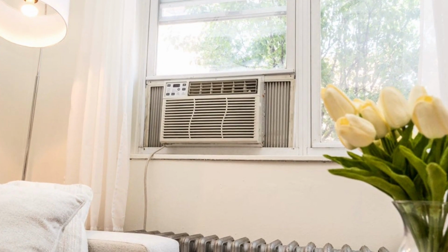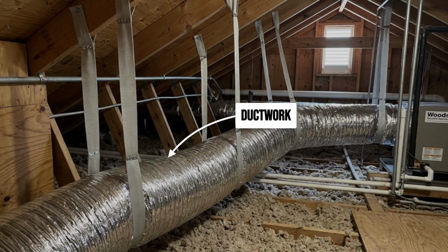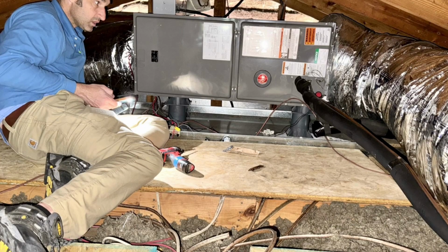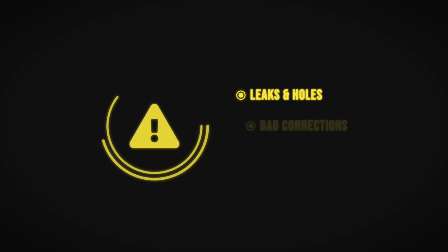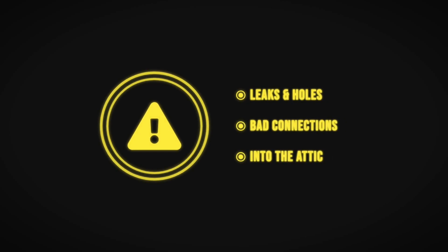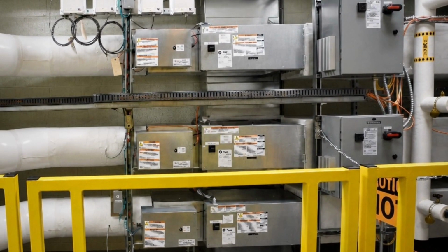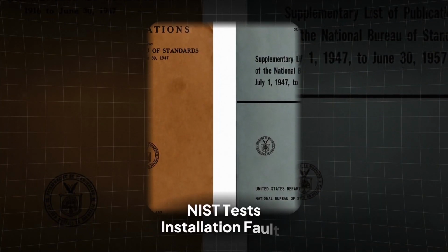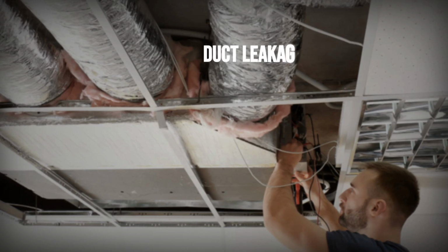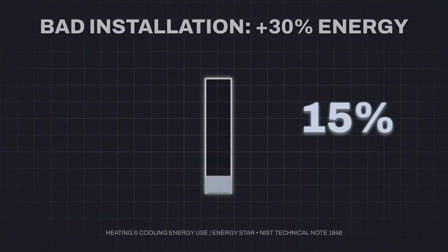So that's the ladder. Now here's the thing that flips it, and it's the ductwork I told you to remember. Energy Star says 20 to 30% of the air moving through a typical duct system is lost. Leaks, holes, bad connections, gone into the attic. And in 2014, NIST, the National Institute of Standards and Technology, published Technical Note 1848, testing installation faults on real equipment. Duct leakage came out the dominant fault, the single worst one. Their finding: bad installation can raise a household's heating and cooling energy use on the order of 30%.